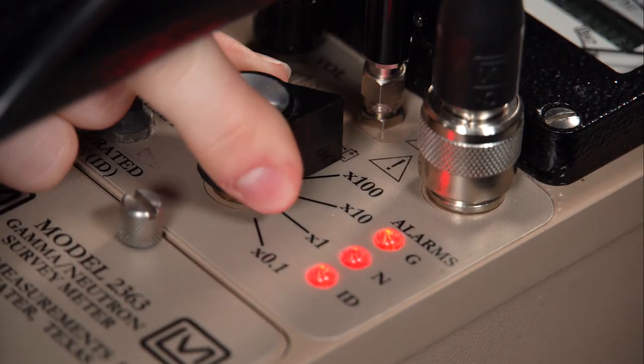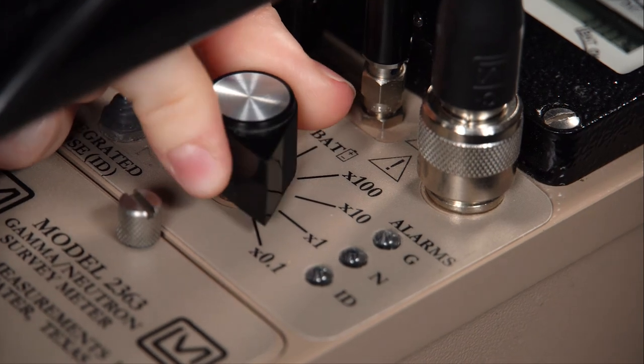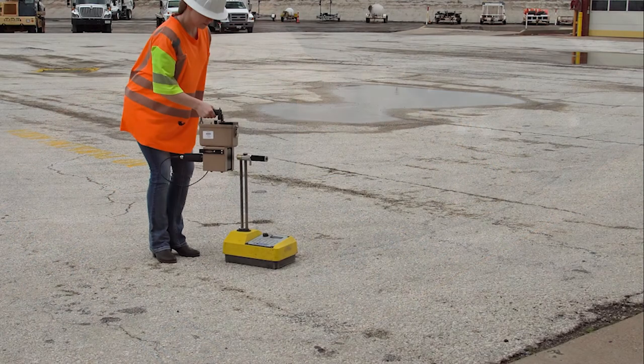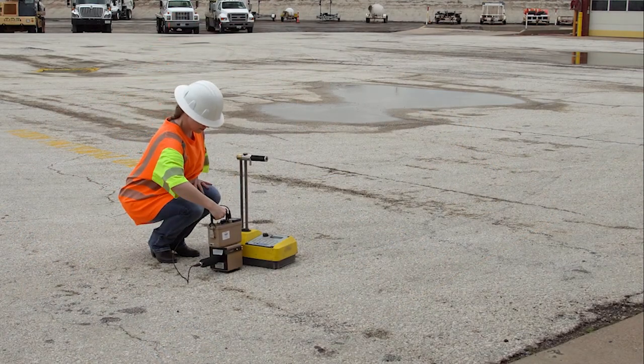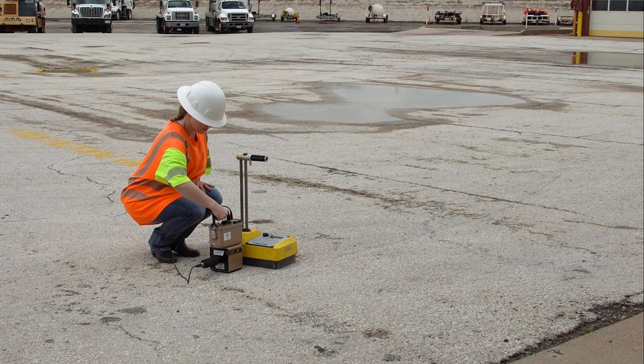Turn the rotary range switch to the 0.1 position for maximum sensitivity or to the range that encompasses your decision level. Point the meter towards the suspected radioactive material and place the front of the detector as near as possible.